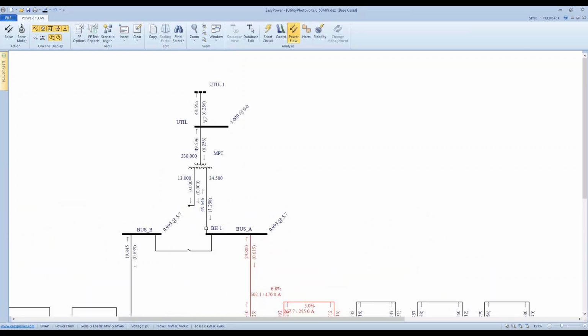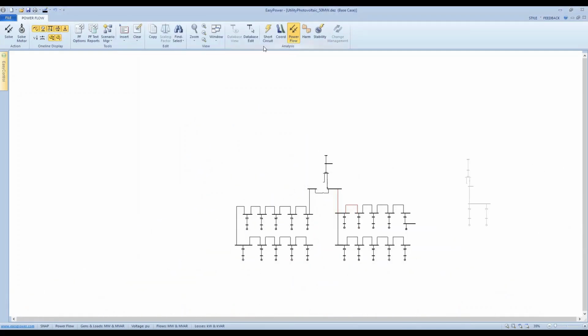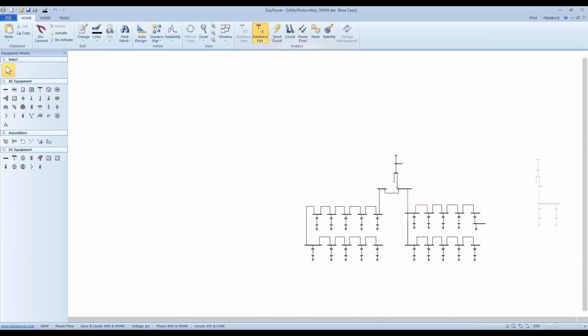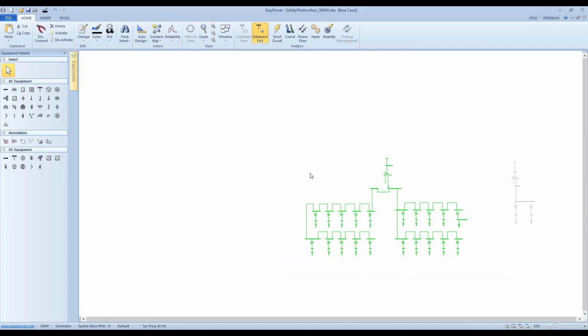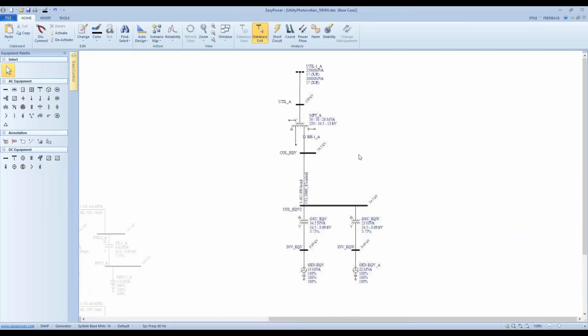So the amount of power I can deliver at the point of interconnection is 49.596 megawatt and 6.256 megavar. That's from my one line power flow calculation result. Now let's go to the lumped equivalence model to see what number we can come up with, if they are the same or how much difference we can observe.